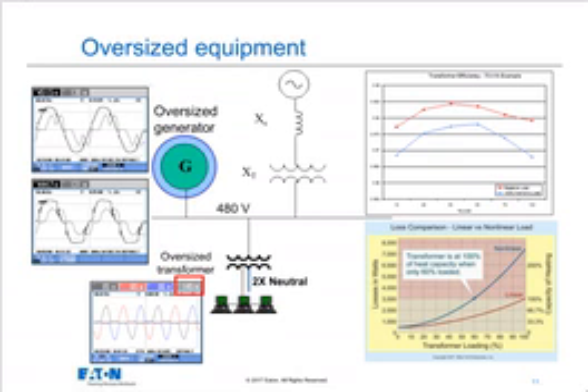Bottom left, we have oversized transformers and 2 times neutrals. So we did some things there to, again, live with the harmonics, the third harmonics, especially on the double-sized neutrals. K-rated transformers, in fact, were essentially like taking a 112.5 kVA transformer and putting a 75 kVA nameplate on it. So you're living with the harmonics. Top right shows that there's a little bit of losses, 1 to 2%.